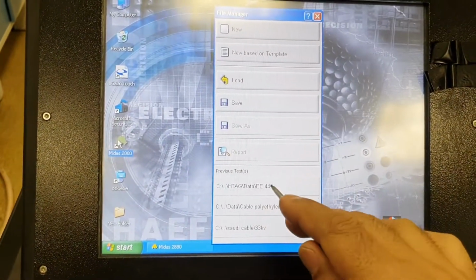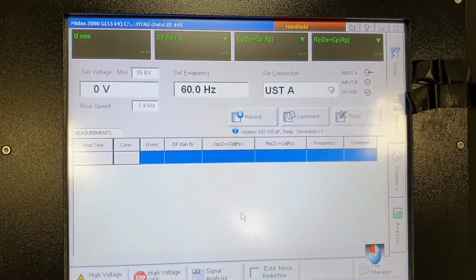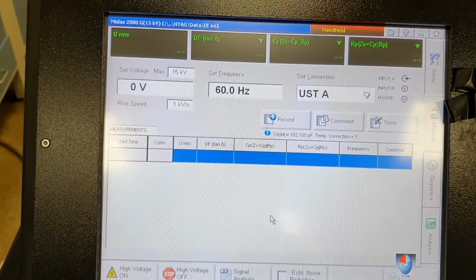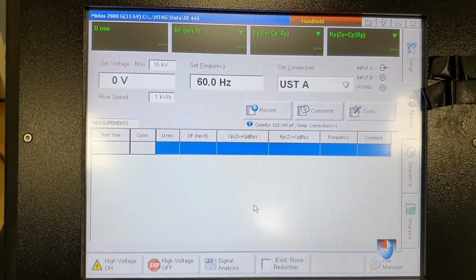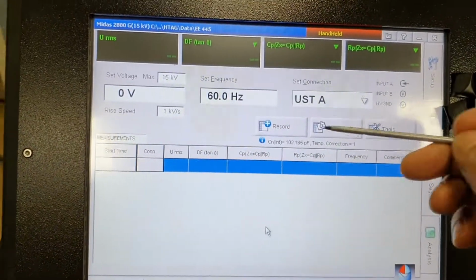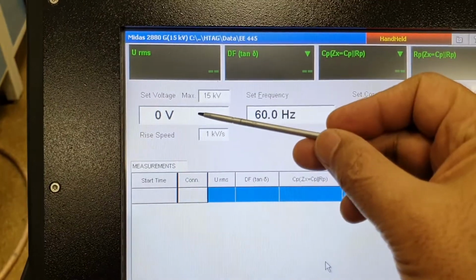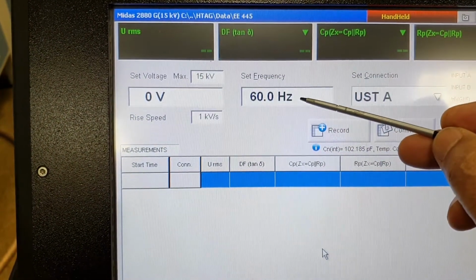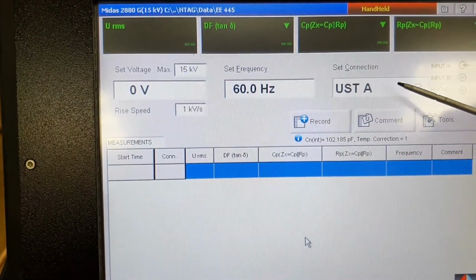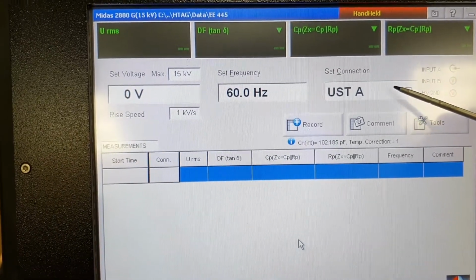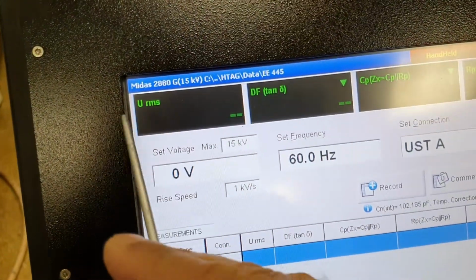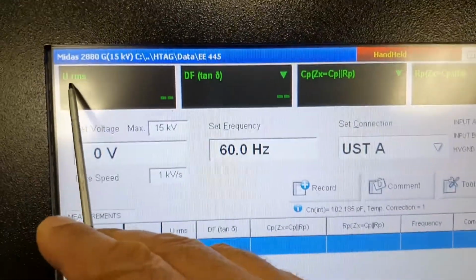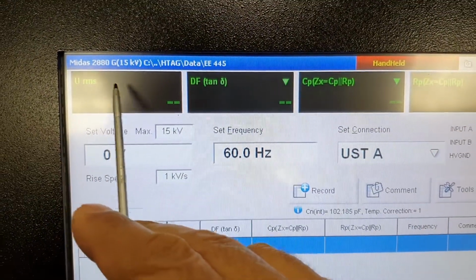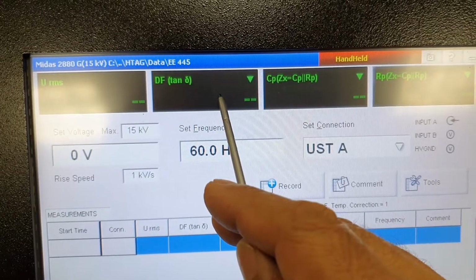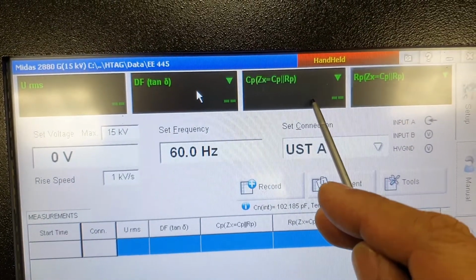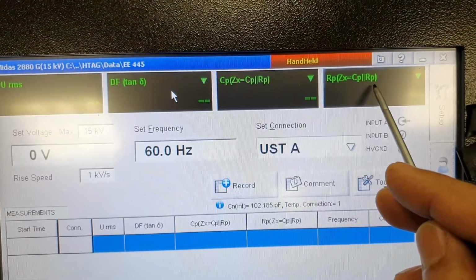When you come for the experiment, you will have a window always open for you like this. You set the voltage, and the frequency is default 60 Hertz. The mode you don't need to change, it's already set. What we'll measure is the applied voltage, RMS voltage, and tan delta, along with capacitance and resistance values.